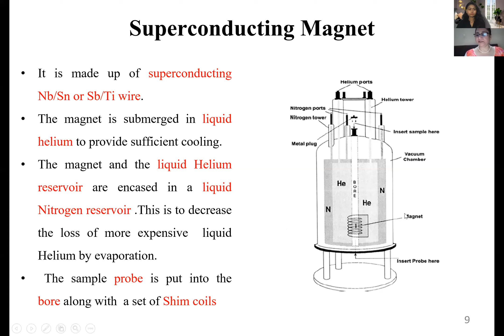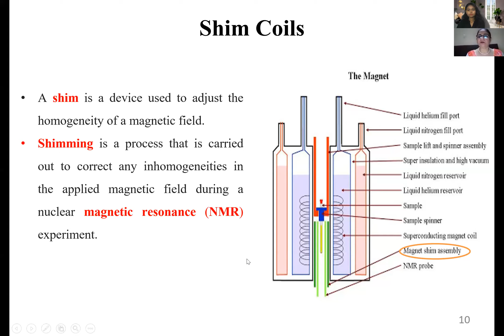These are the shim coils. This is a cross section of the previous figure. Here you have the probe, or NMR probe, and next to the probe you can see the magnet shim assembly. What are shim coils? These are basically devices used to bring homogeneity to the magnetic field, because we need a homogeneous magnetic field when the sample is placed in the sample tube or in the probe. Shimming is a process carried out to correct any inhomogeneity in the applied magnetic field during a nuclear magnetic resonance experiment.